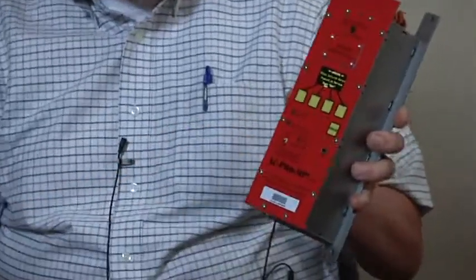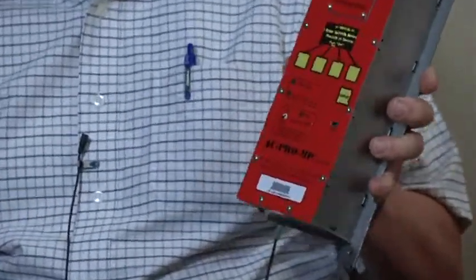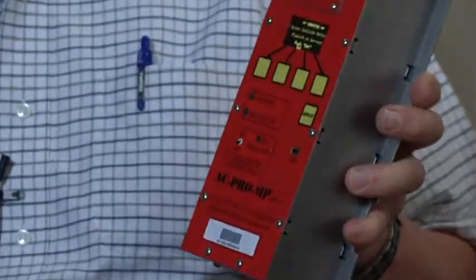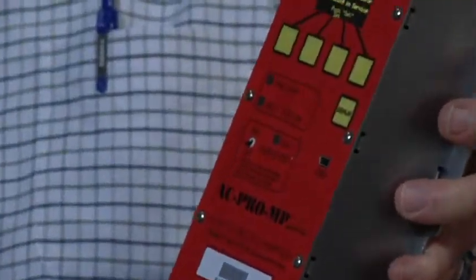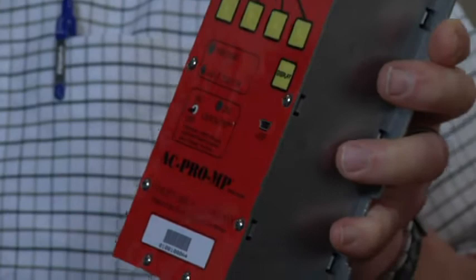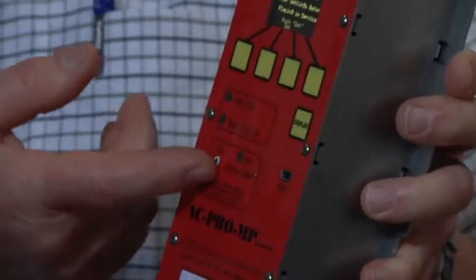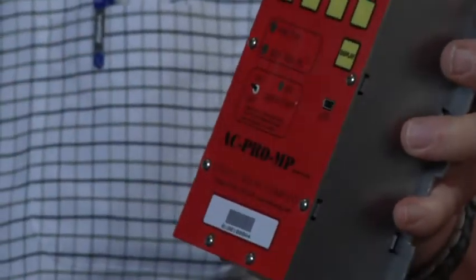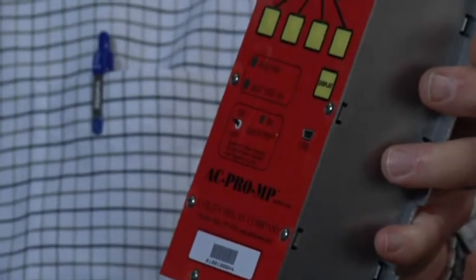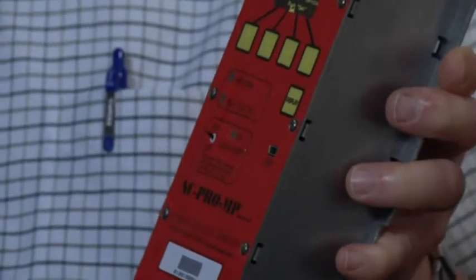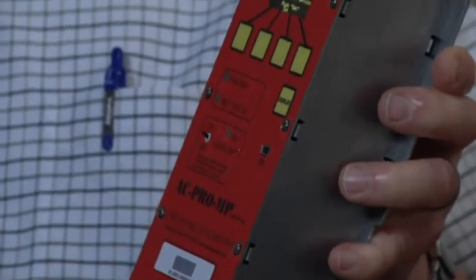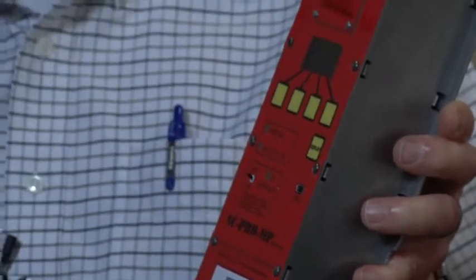And one of them is Quick Trip. There's a little Quick Trip switch that turns that function on and off, and that's for arc flash reduction. So when somebody's working downstream, racking a breaker in or out or other work, they turn Quick Trip on, and that reduces the arc flash hazard in case there's an accident. Then it reduces the risk category.